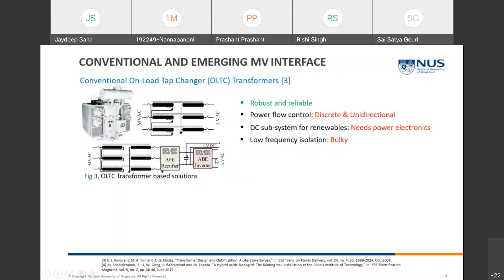Now, there are some concepts that have emerged in the last decade or so, and have also been realized, known as the solid state transformer. It would have a medium frequency isolation for providing the galvanic isolation, and on either side you would have power electronics, and these days they're going for wide bandgap power electronics like silicon carbide MOSFETs, so that you can have good efficiency as well as power density. Here it usually negates all the disadvantages that the OLTC transformer-based solution would have. So you can have continuous and bidirectional power flow control.